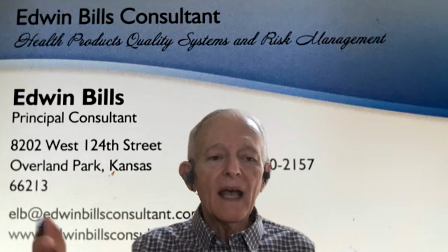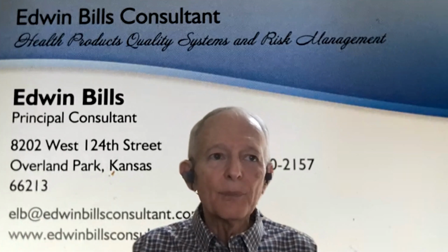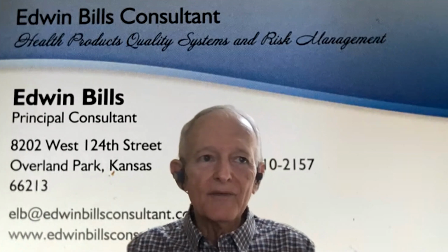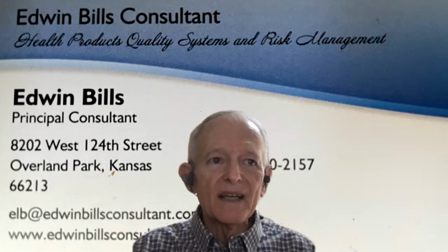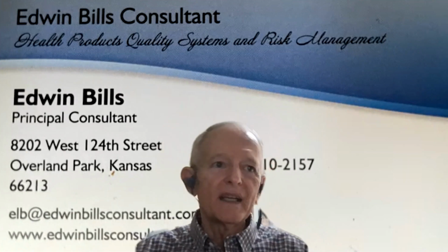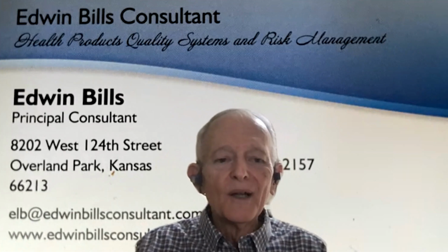Right. And then you need to confirm it in the post-production phase. So as you get information, and we haven't talked about that, but now the standard says you need to have an active process of gaining post-production information. So you need to be going out there and looking to see how your device is used, and if it's used according to what you thought it should be, and what benefits are being confirmed, and those sorts of things. So you're not done at the end of design development when you throw it over to manufacturing. You have to continue monitoring throughout the life of the product.